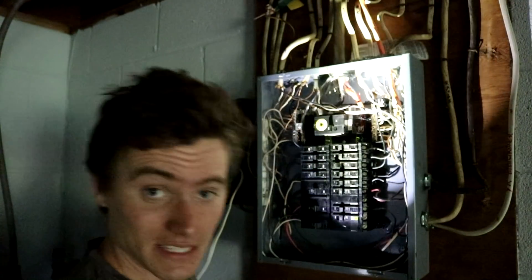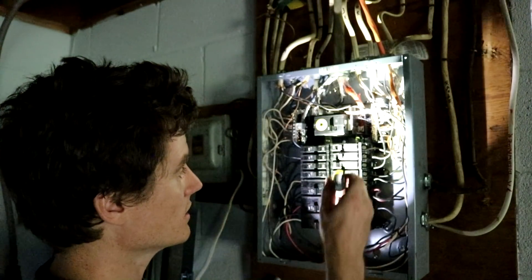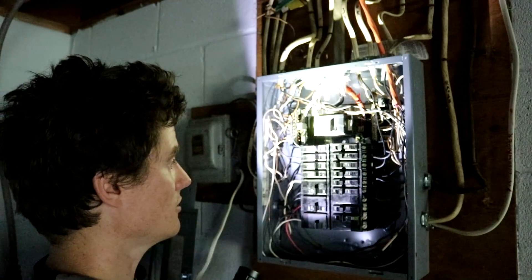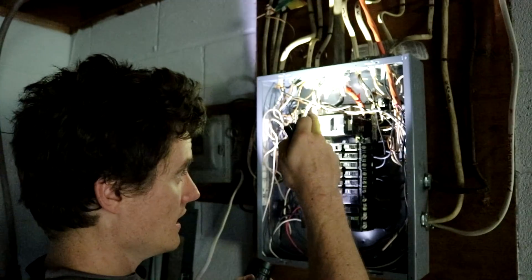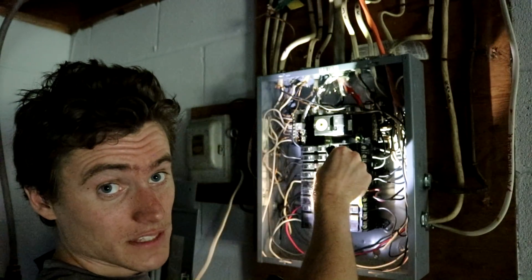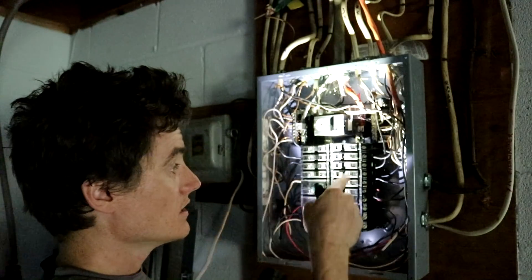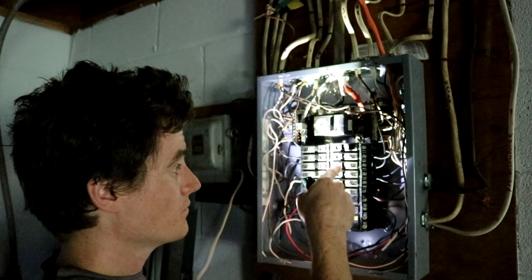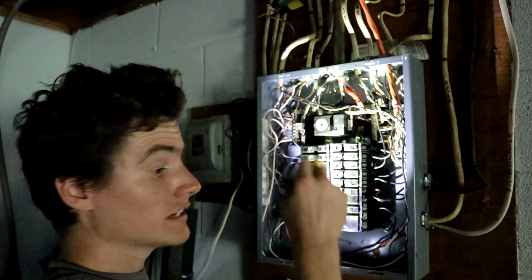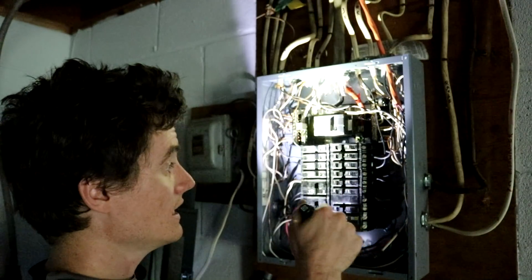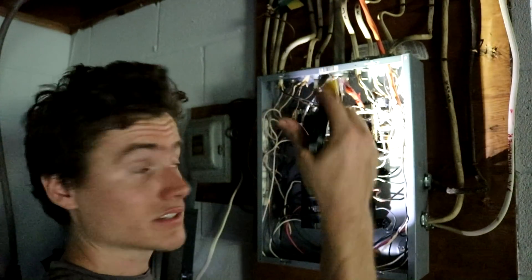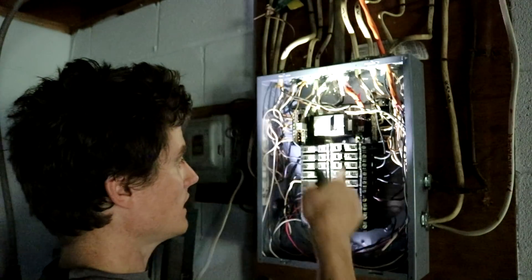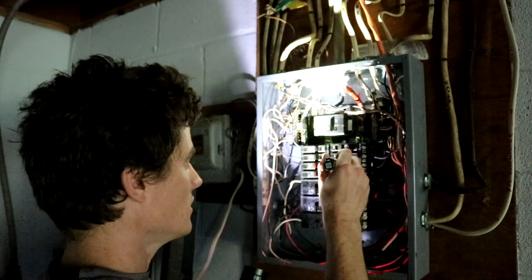So what I did is I came in here and I just numbered all the breakers the same as the wires. But you can't always trust that. You need to check it. So then I'll come down to the third breaker and check that one. So the third breaker is now supplying with it on. If it's off, it's just going to be to that wire alone. So when I'm first checking, when I first plug it in, I have all the other ones turned off and I can go around and check those outlets real quick. And whichever outlets or lights turn on signifies what's just on that wire.